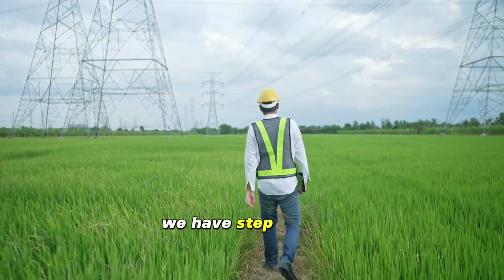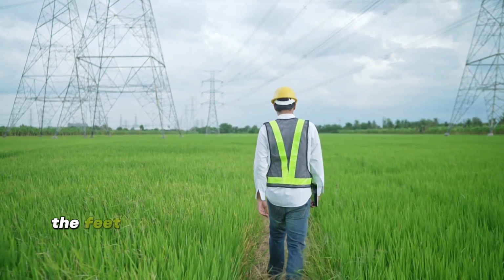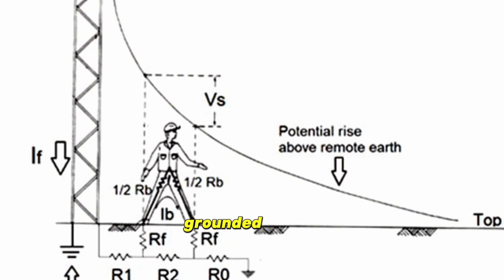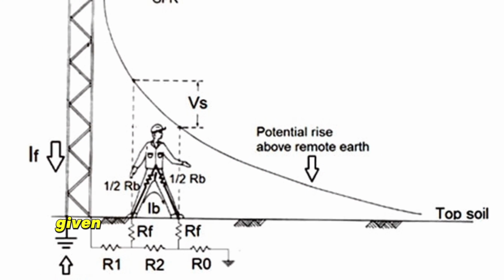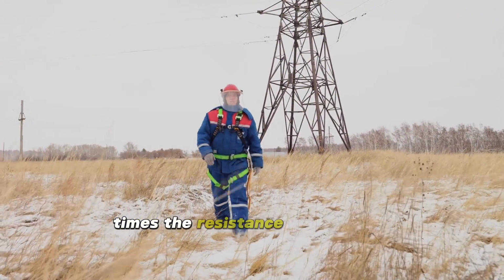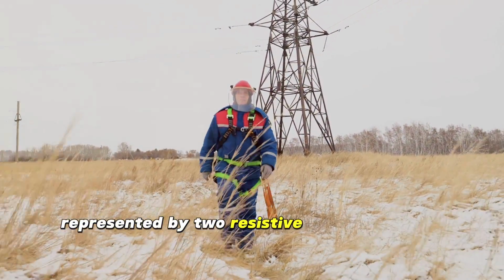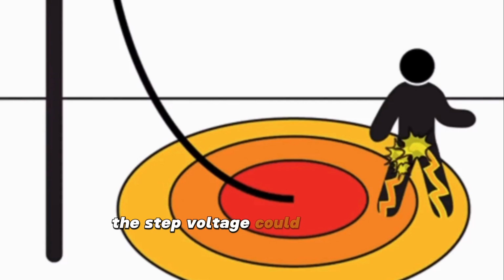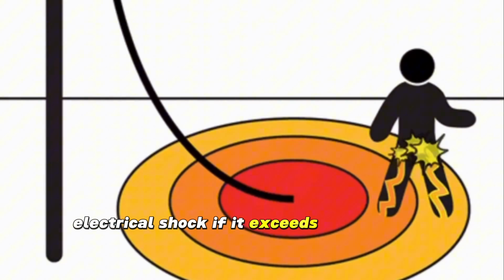On the other hand, we have step voltage. This is the potential difference between the feet of a person standing near an energized grounded object. It's equal to the difference in voltage, given by the current flowing between the feet times the resistance of the earth, represented by two resistive voltage dividers. The step voltage could also cause electrical shock if it exceeds safety limits.